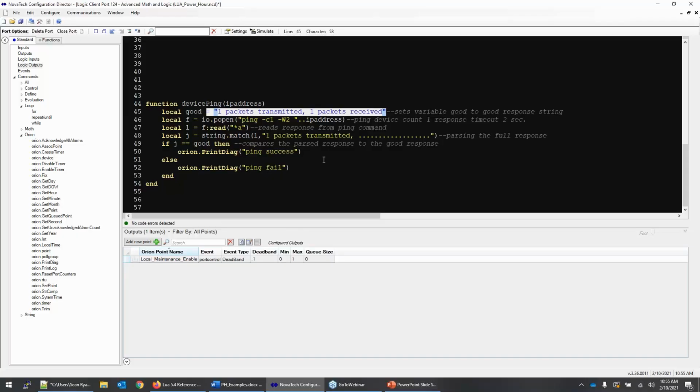And so this is a way to do a quick ping check from the Orion to other devices, and you can bring those results back and use them within the Orion. Obviously you have COM fail points and whatnot that are built in as you create your DNP ports or whatever else inside the Orion, but you can extrapolate this and use it for basically non-SCADA type devices.